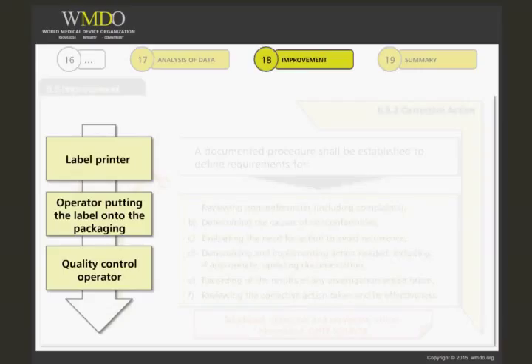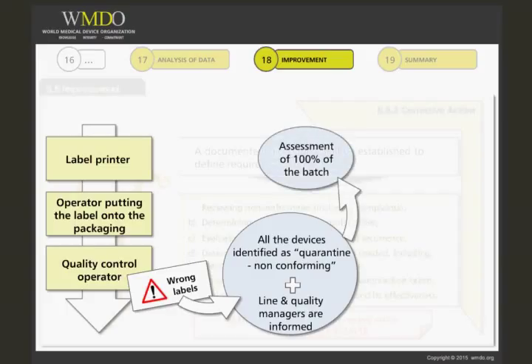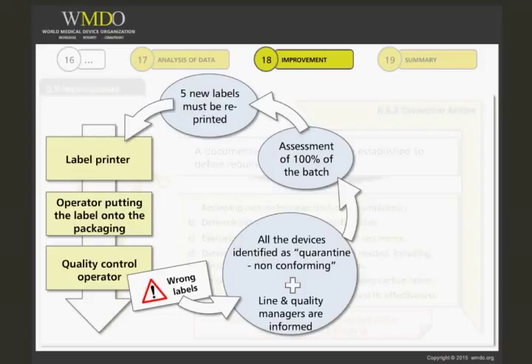The quality control operator detects that certain labels of the batch assessed are the wrong ones, related to another batch. He stops the line and identifies all the devices as quarantine non-conforming products. The quality control operator calls his line manager and the quality manager to assess the situation. According to their process, they initiate a CAPA procedure. After an assessment of 100% of the batch of 50 devices, the quality manager, the control operator, and the line manager determine that 5 labels out of 50 printed for the batch are wrong. They confirm it is only the wrong label — the products and the batch are the right ones. They decide to print 5 new correct labels and replace the wrong ones, so they can release the batch from quarantine and put it in the final goods store.